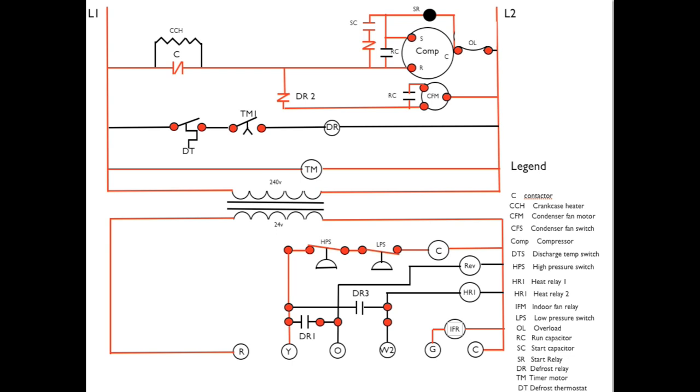Okay, this is sequencing on a call for first stage heat on the heat pump. Starting in the low voltage, power will pass from R to G to energize the indoor fan. This energizes the indoor fan relay, which energizes the indoor fan.